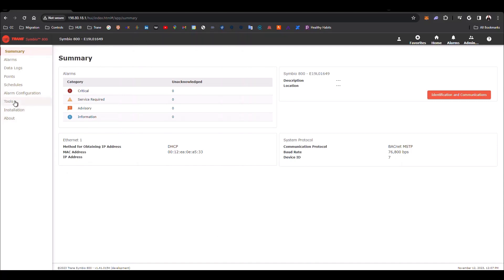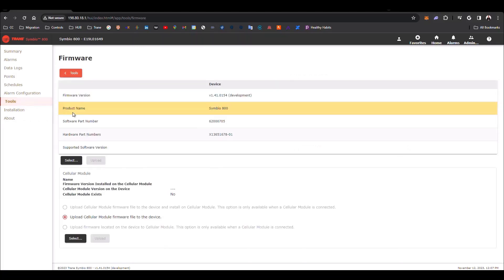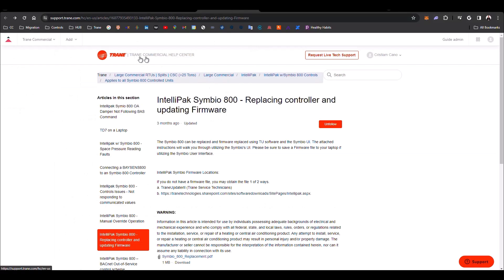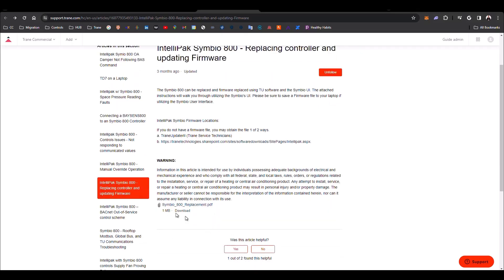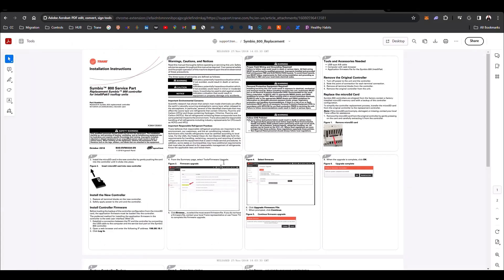We are going to review in Tools again, then Firmware, and this is the new version of your firmware. Before ending this video, I would like to refer you to this document in our Trane commercial help center. This is an article that shows you the procedure to replace a controller and upgrade the firmware for the IntelliPak Symbio 800. This document shows you the way to upgrade the firmware and helps you change the controller, upgrade the firmware, take a backup, and upload that backup to the new controller.